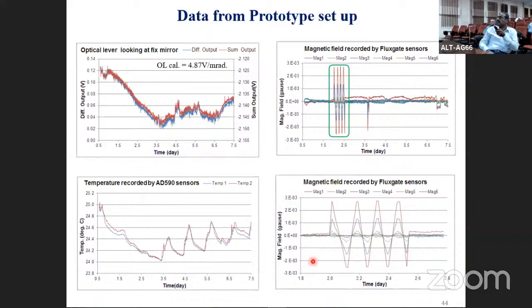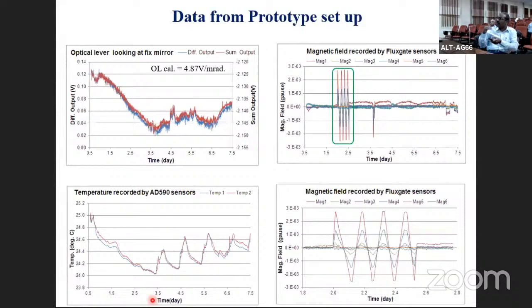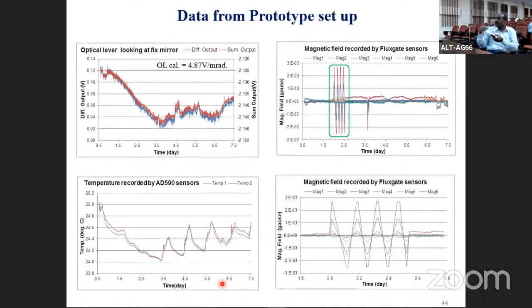We use 6 flux gate sensors, and all of them are showing the signal. You may be wondering why there are different levels. The reason is I have put these sensors in a stack inside a magnetic shield, so the penetration of the field decreases going into the center. The center one is showing very little field, while the extreme ones are showing a large field. I thought I would share with you the beauty of the measurement instrument we have, its resolution and its capabilities, what we have built. And I'm proud to be part of this.